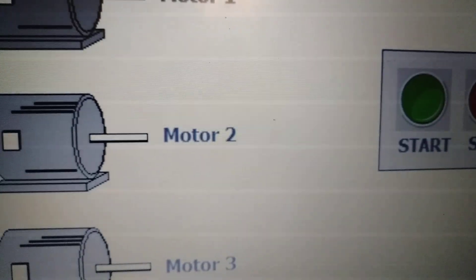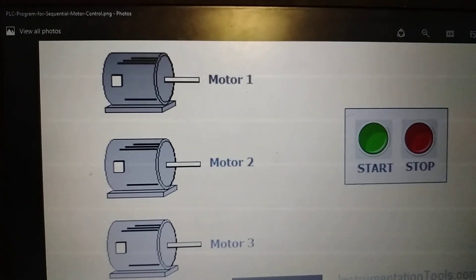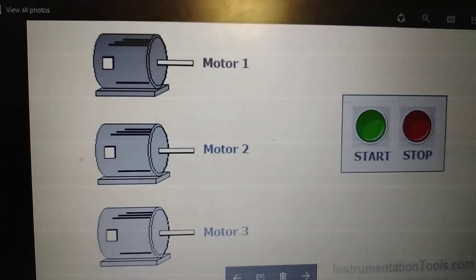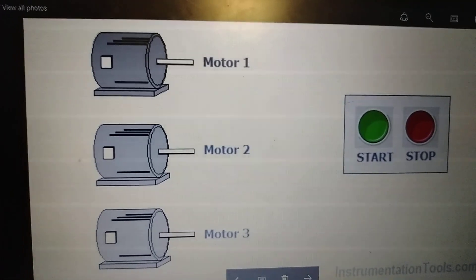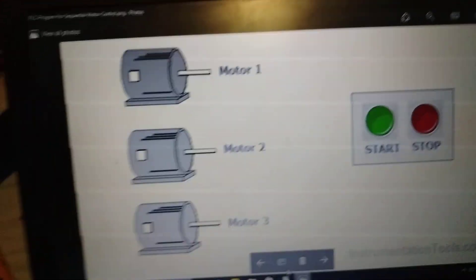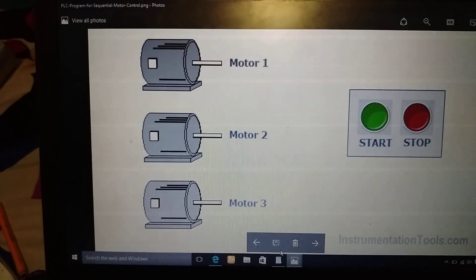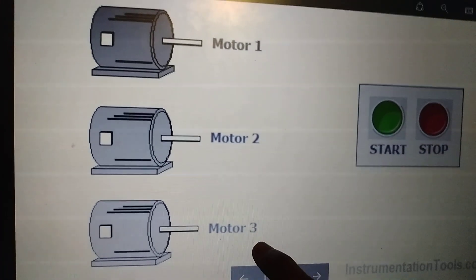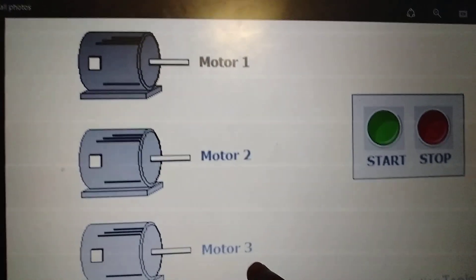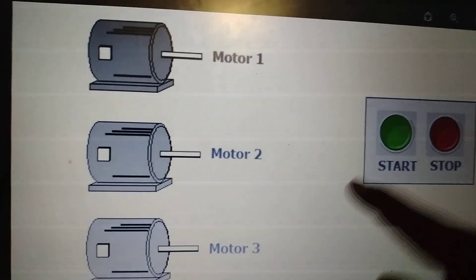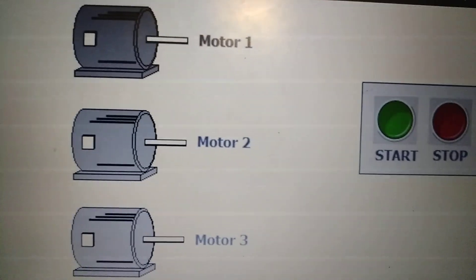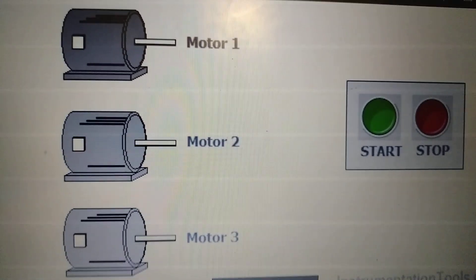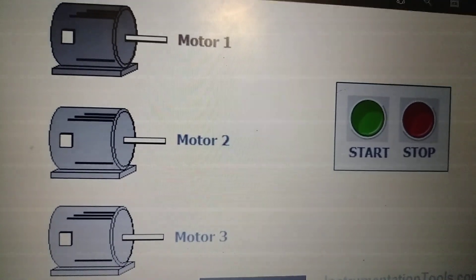This problem can be solved by using a PLC program for sequential motor control. In this example, we consider three motors which are going to be controlled in sequence. Motor one will start, then after some delay period motor two will start, and after another delay period motor three will start. The whole operation takes about 10 seconds to start all motors sequentially. By using the delay, we can avoid the problem of consuming large power.